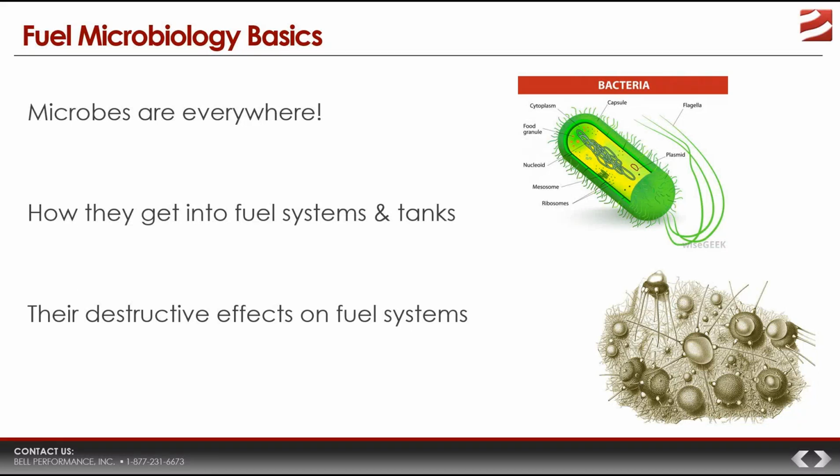You will have situations where microbes will actually consume the lighter end hydrocarbons in both diesel, but especially in gasoline, and that changes the properties of the fuel, especially with respect to its vapor pressure and its viscosity. Now, when you talk about the tanks and the fuel systems themselves, microbes cause delamination of tank linings, destruction of fiberglass surfaces by fungi.